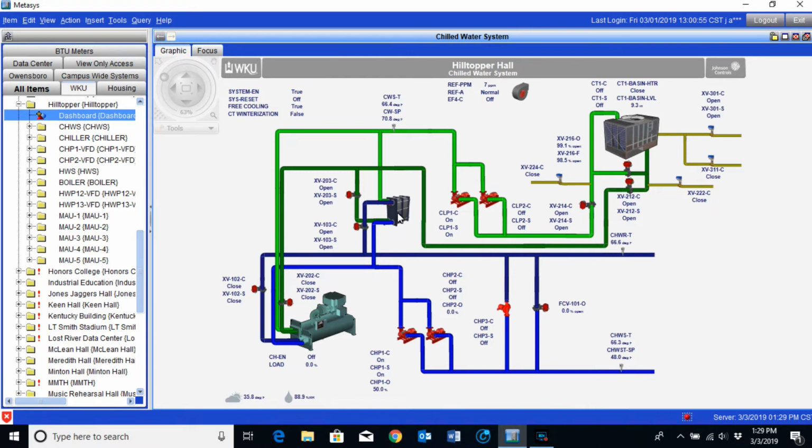We will then close the isolation valves on the heat exchanger, open the isolation valves on the chiller, and then run the chiller. Some of these systems can actually maintain a decent amount of chilled water even when the weather warms up. We have some systems that will actually provide adequate chilled water even when we get to around 60 degrees. Now, they cannot do it for an extended amount of time, but on those days when temperatures reach around 60 or so, those buildings seem to maintain fine, and we can keep the chiller down a little longer and actually capture that cost savings.